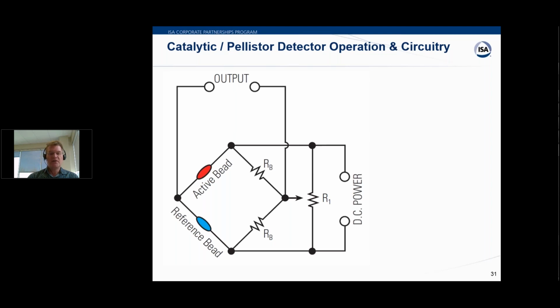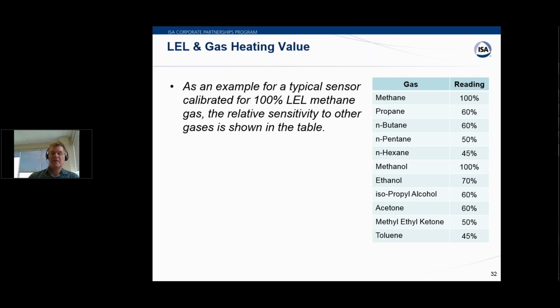So we have an uncoated reference bead that compensates for changes in ambient temperature. And then we have the catalyzed bead. So we're just measuring on those two sides. Nice fast response time on these, 10 to 15 seconds. Repeatability is pretty good, and they drift about 5 to 10% per year. And that's just part of the challenges with a catalytic, right? Largely because the catalyst could be contaminated.